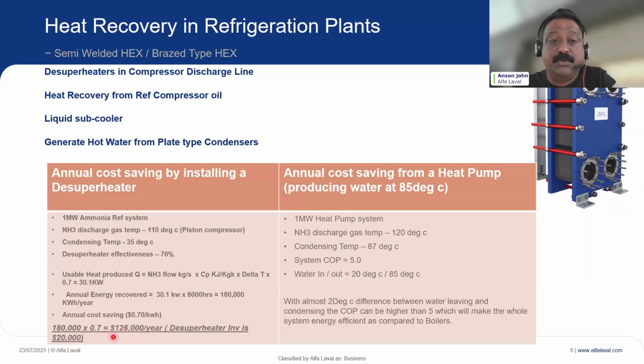At the same time, when you have a de-superheater in the system, of course, your condenser can be much smaller because your inlet temperature to the condenser is going to be pretty low. It's not going to be 110, it's going to be maybe 50 degrees C or something. So that's another saving. And since you are not going to have a high inlet temperature into the condenser, the scaling in the condenser will be much lower. So we are talking about much saving on the maintenance of the condenser as well. So there is a lot of saving there.